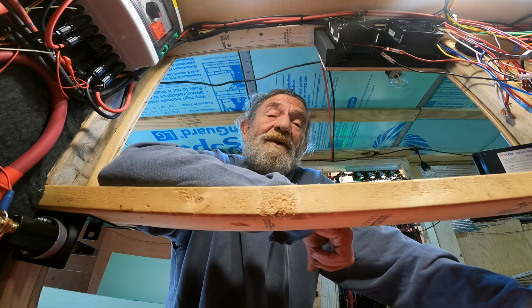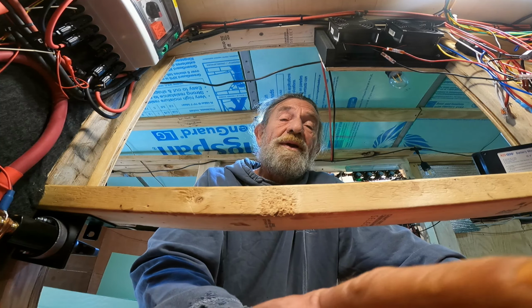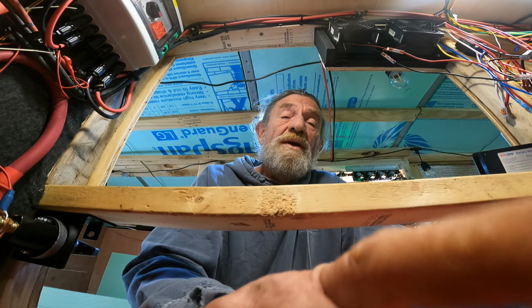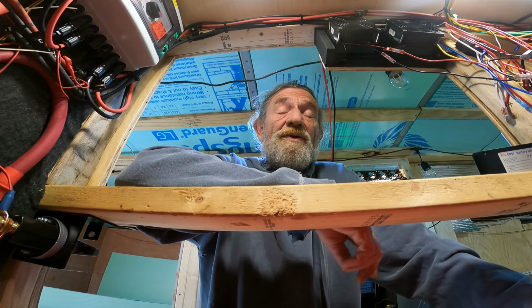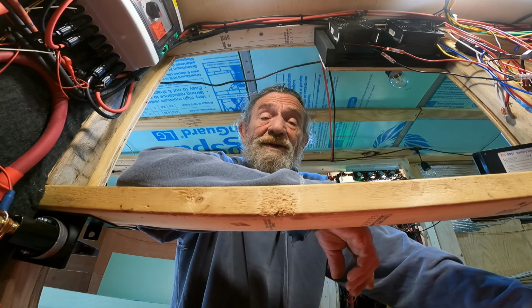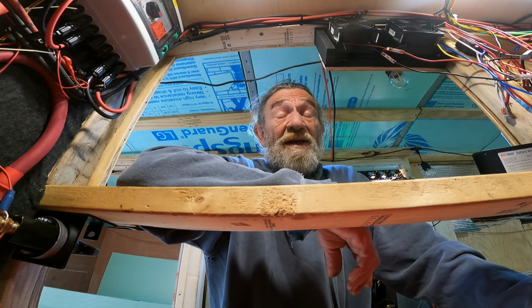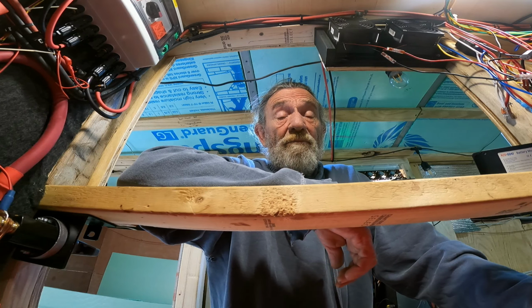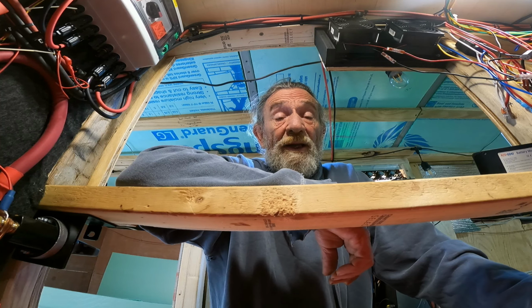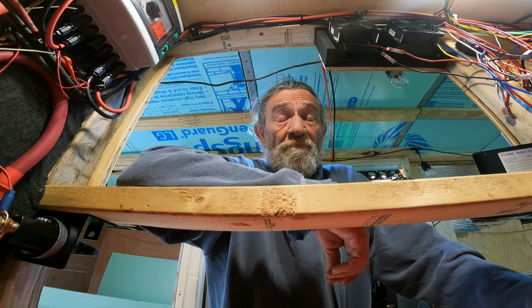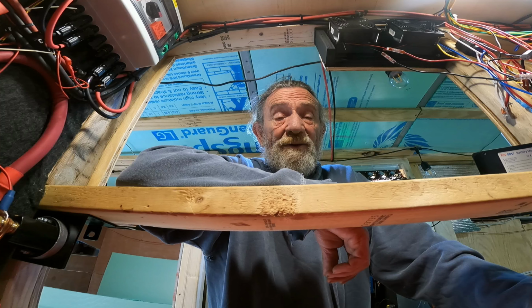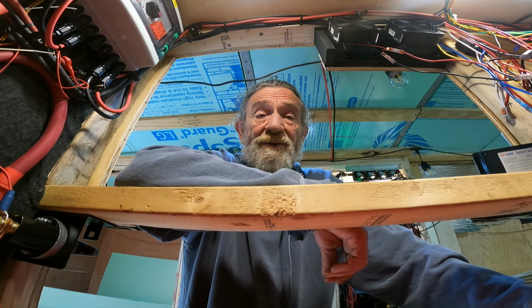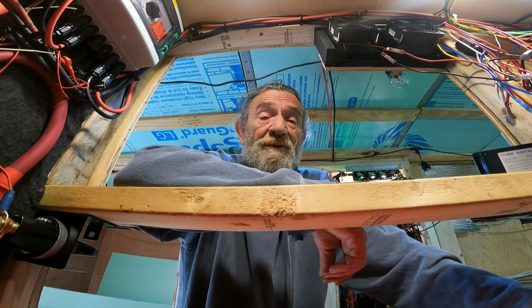One of the other things I realized in all of my work connecting all of those connectors is that there are three possibilities for connections on the Cerbo GX with regard to Ethernet type cables. One is BMS CAN, which in my instance is all the way on the right, and there's two ports for that. In the center is VE CAN, and then on the far left side of the Cerbo GX, the way it works in my installation, was VE bus.